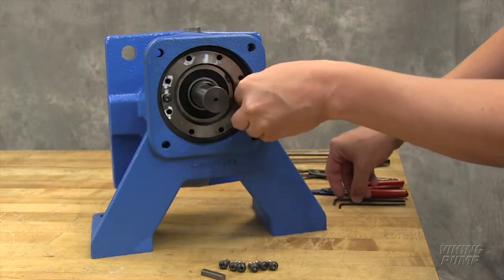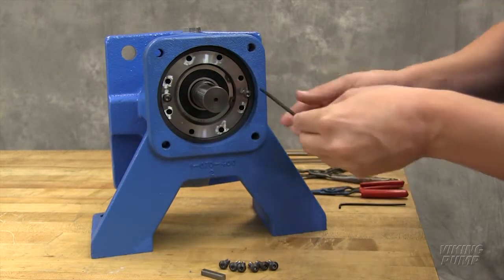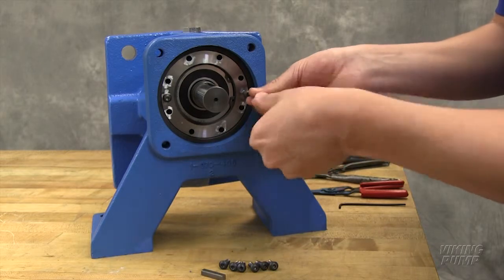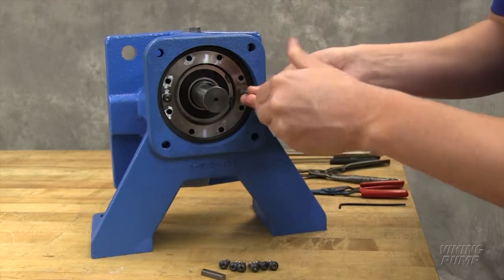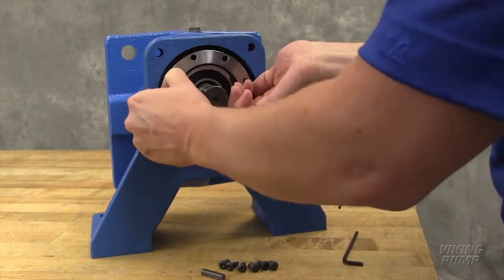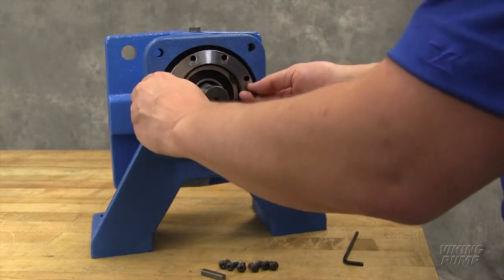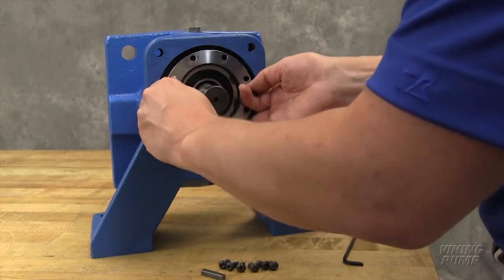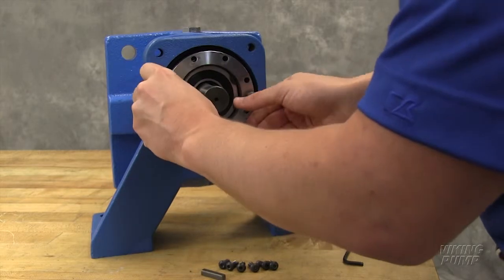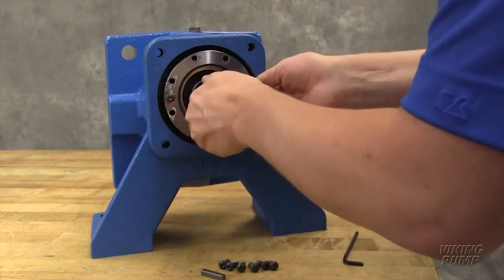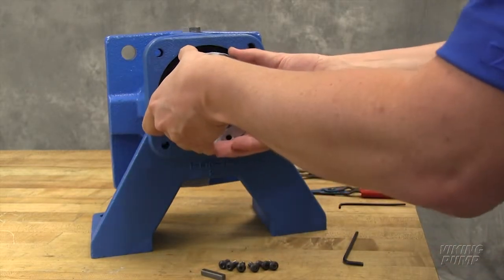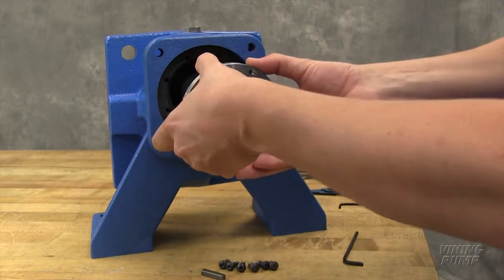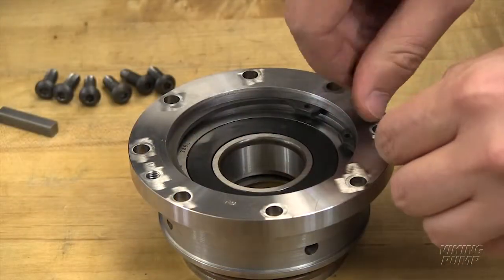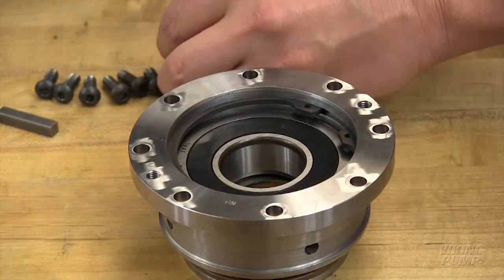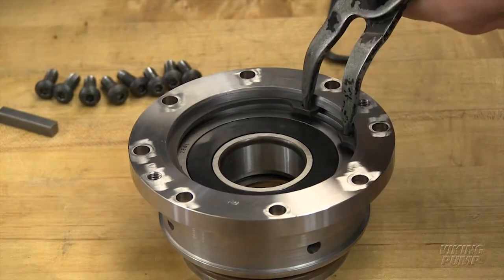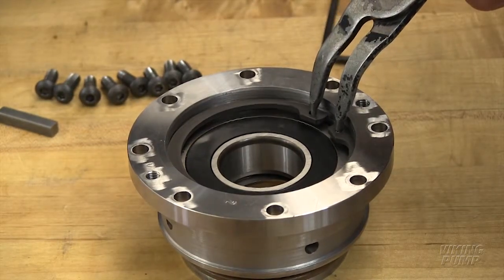The thrust bearing and the bearing shims will remain in the seal holder. These need to be removed prior to reassembly. Also, the stationary seat of the seal will be left on the shaft and kept there by the retaining ring. The stationary seat is a slip fit into the seal holder. The only resistance to its removal will come from the O-ring on the outside diameter of the stationary seat. Use the snap ring pliers to remove the retaining ring from the seal holder.